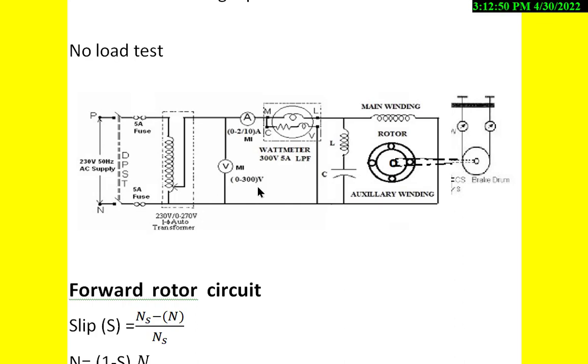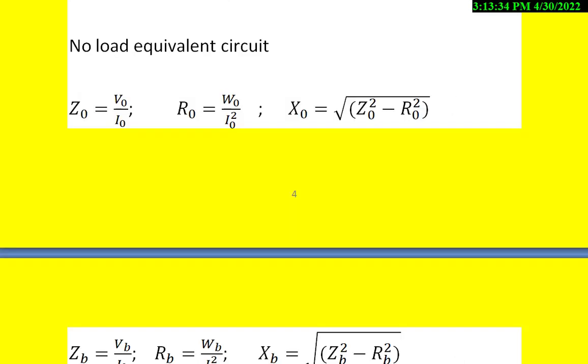Under this no load test condition, the voltmeter reading is represented with V0, the ammeter current is represented with I0, and the wattmeter reading is represented with W0. Once the meter readings are known, then the no load impedance of the single phase induction motor can be obtained like this: Z0 is equal to V0 by I0. Similarly, the no load resistance R0 is obtained by W0 by I0 square. Once this is obtained, the no load reactance can also be obtained using the formula X0 is equal to the square root of Z0 square minus R0 square.